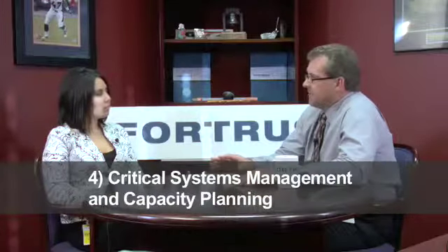The other thing we do, and I think we're really good at, is managing capacity. That means loading our UPSs to 50% versus 100% load. All our equipment is designed with N+1 redundancy or better, but we don't infringe on those redundancies just to provide extra capacity.